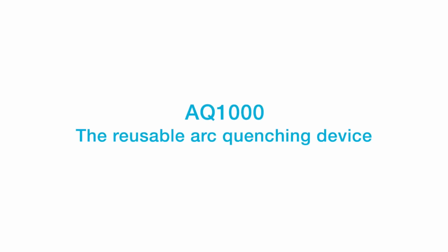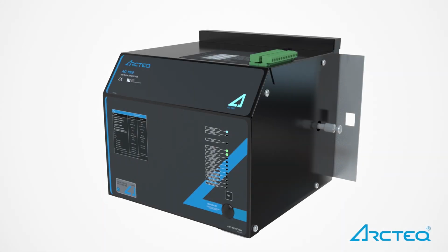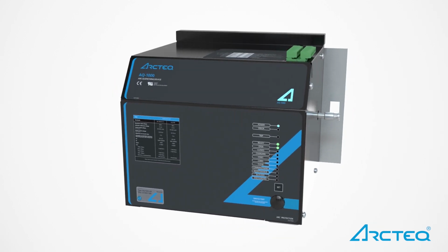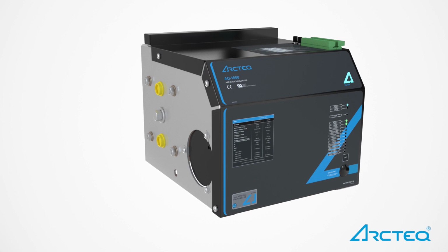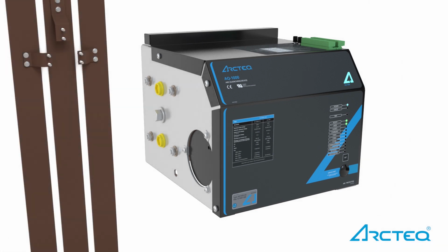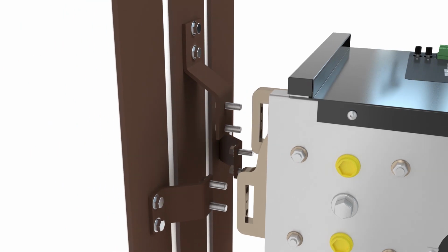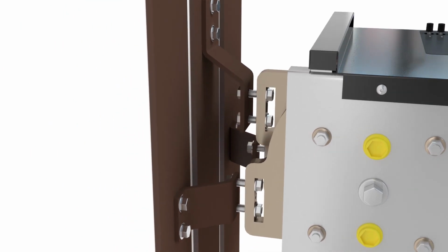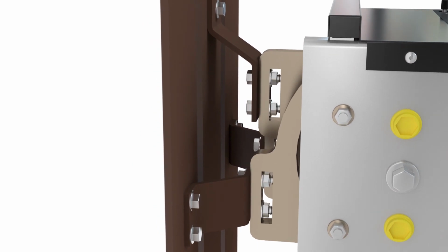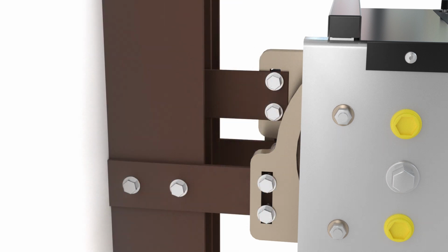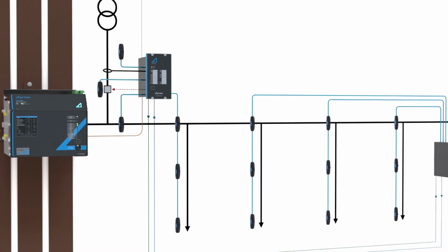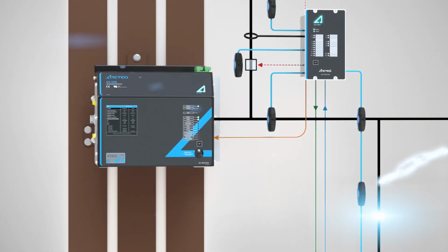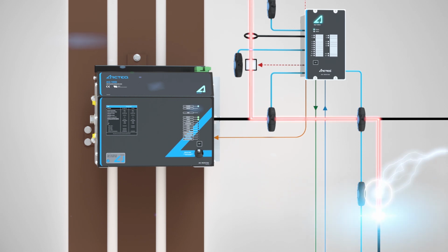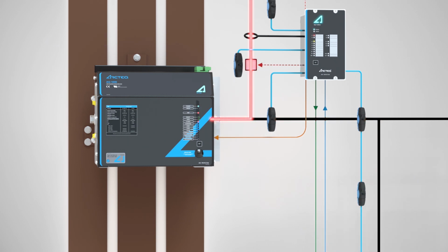The AQ1000 arc quenching device, the latest protection innovation from Arcteq, the pioneer of arc flash protection. Active arc quenching is the most exciting new solution for improving personal safety, maximizing asset reliability, and minimizing downtime. The AQ1000 can be applied to protect any system with up to 100 kiloampere and 690 volt rated equipment. The arc quenching device is bolted to the bus bars in the most practical location, typically close to the main circuit breaker. The AQ1000 adds to the well-proven AQ100 arc flash protection system. The AQ100 system senses the arc and initiates rapid arc quenching sequence, creating a controlled low-impedance path, transferring arc fault current to the quenching device. All this occurs in less than 4 milliseconds.